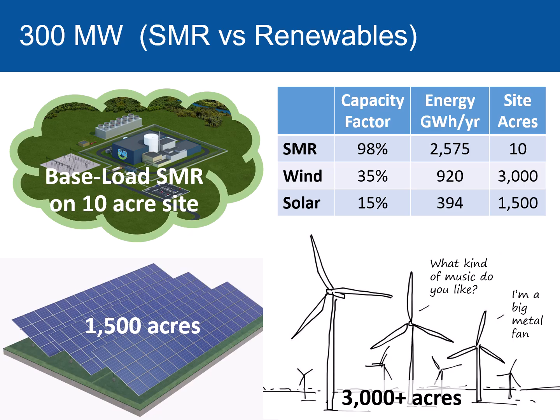300 megawatts is the power capacity of wind and solar. A good wind site might be in the 40%, or 35%, capacity factor range, producing about 920 gigawatt hours a year. Depending on your spacing, you're going to need about 3,000, 4,000, 5,000 acres.